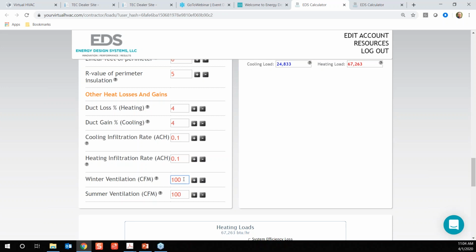So if I'm going to be heating that up with the ERV waste heat from 3 degrees up to, I don't know, 50 degrees, let's make my life easy. Let's say it's 0 degrees outside and it's 70 degrees inside, and I'm going to take my ERV up to 50 degrees. So I'm raising from 0 to 50 degrees. So that's getting me 50 of the 70-degree delta T, 5/7 of the way. So 5/7 of 100 CFM is what I'm actually getting heated up.